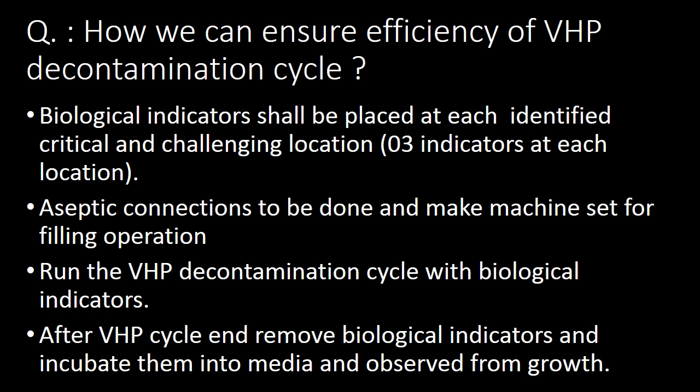In the second step, aseptically connect all machine setup and make the machine ready for filling operation. In the third step, run the VHP decontamination cycle with biological indicators. In the last step, after end of the VHP cycle, remove the biological indicators and incubate them in media and observe for growth.